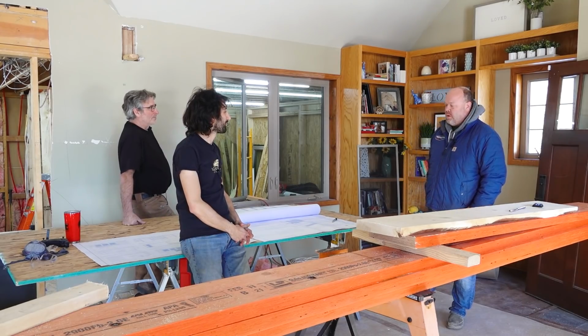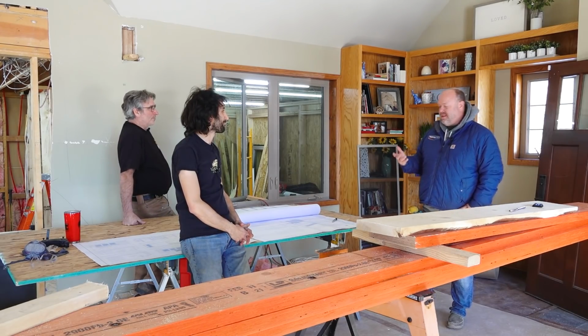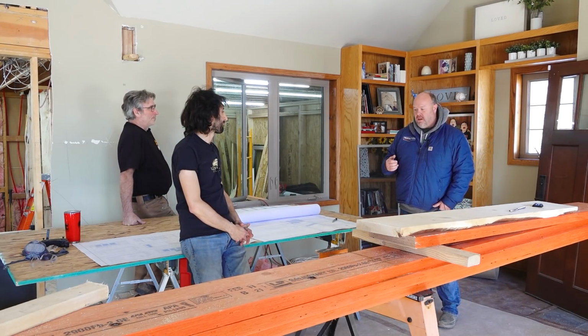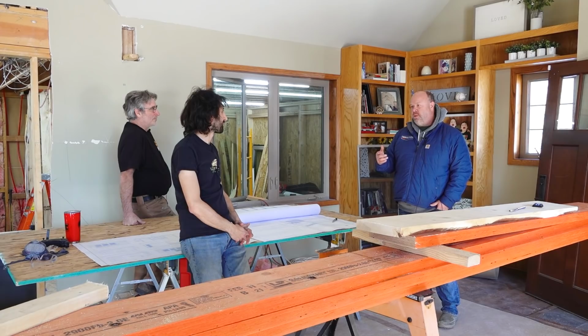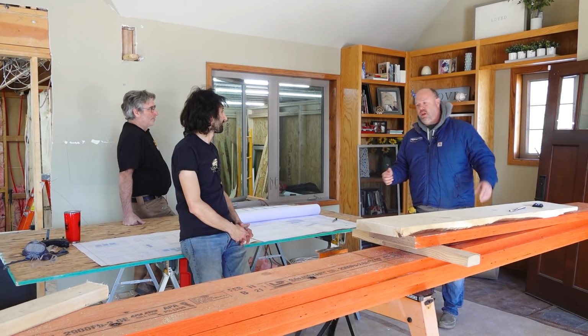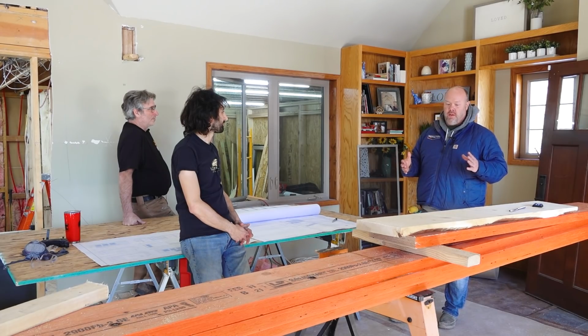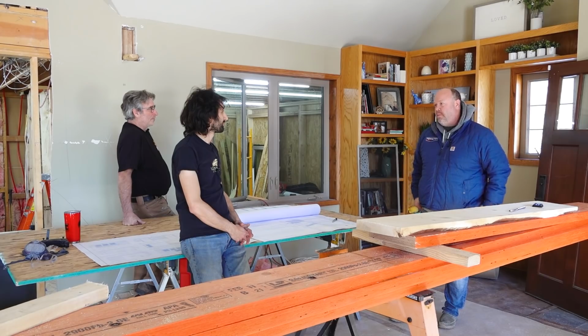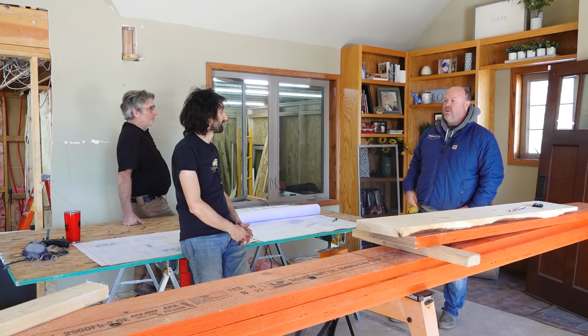That's a great question. If you're doing a full load calculation, there are two different ways. You can do an envelope approach, so basically outside walls, that's my loss. Or you can approach it in a much more refined method, a room by room method. Doing it by room, it actually gives you the CFM per room needed to achieve the loss or gain of that room.